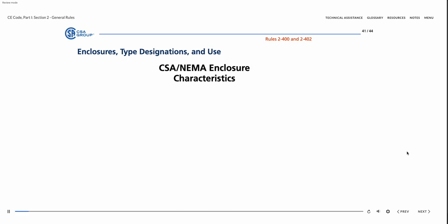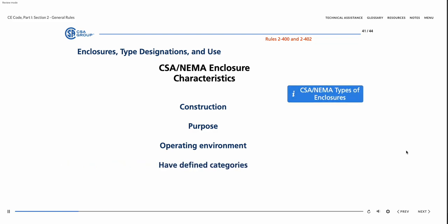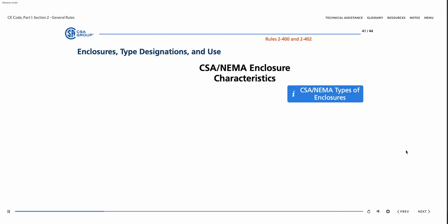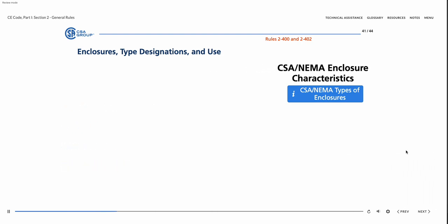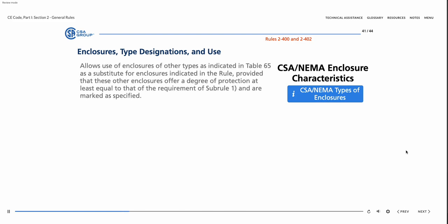CSA NEMA enclosure characteristics. Equipment enclosures vary in construction, purpose, and operating environment. Forms of enclosures are divided into defined categories, allowing for ready recognition and proper application. This rule lists the CSA types of enclosures intended for particular locations. The rule also allows use of enclosures of other types, as indicated in Table 65, as a substitute for enclosures indicated in the rule, provided that these other enclosures offer a degree of protection at least equal to that of the requirement of Subrule 1, and are marked as specified.